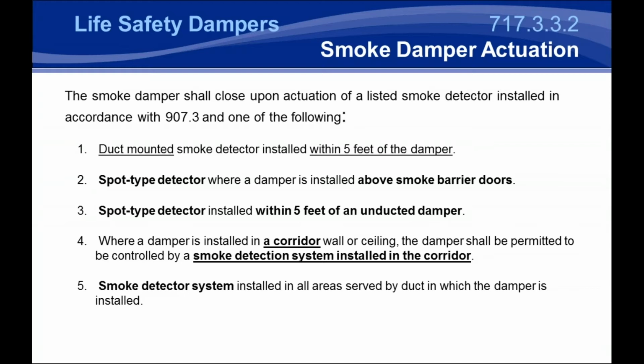Typically, the ones that are addressable are supplied by the alarm contractors, and they're very specific because they have to tie into the smoke control system and the overall control panel. Because of that, if you order smoke detectors that are mounted by us, we have to tie it into the damper to make sure that damper shuts down. And it will shut the damper down without a signal back to these systems. The damper, if used in a smoke type system, will have damper operation indication, so you will know if the damper is open or closed, but you won't have an addressable smoke detector that will tell you where smoke is detected in the building.